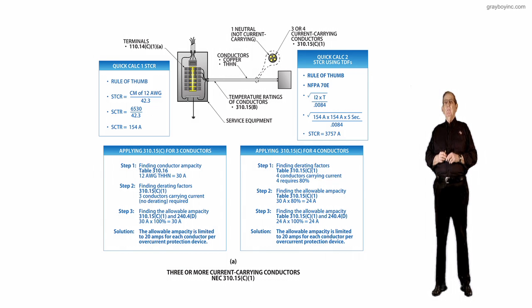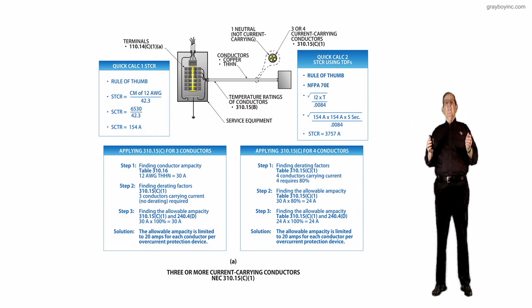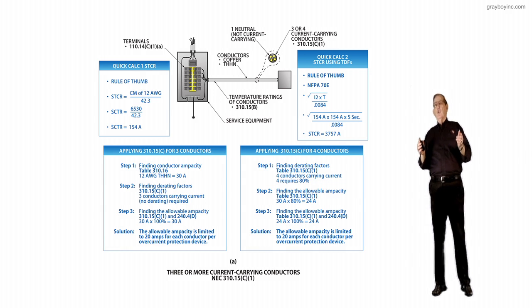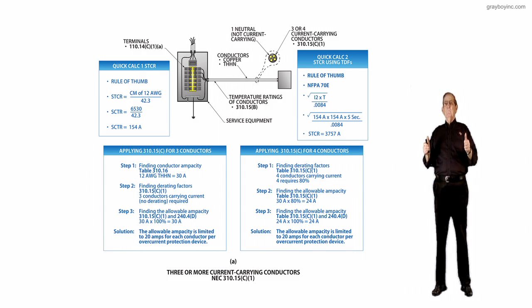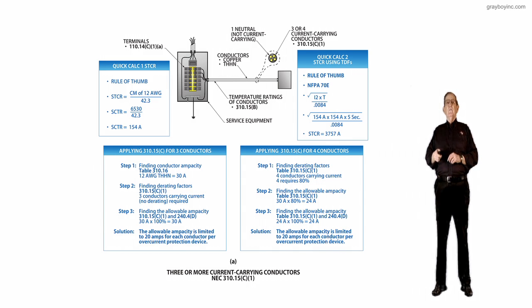Now if you wanted to look at a situation where the inspector would want to know how many amps you have for short-time current rating or long-time current rating. This is kind of a rule of thumb, but if you look at the short-time current rating, you would take the circular mil of a number 12 wire from table 8 of chapter 9, and you'd find it's 6,530 circular mill. The divider that you use is 42.3. You do your math, and it'll pull 154 amps for about 5 seconds.